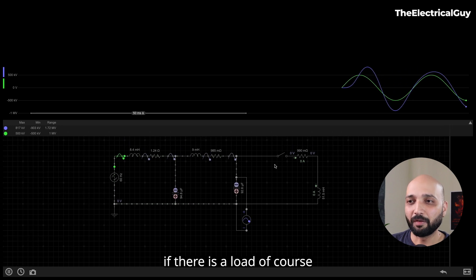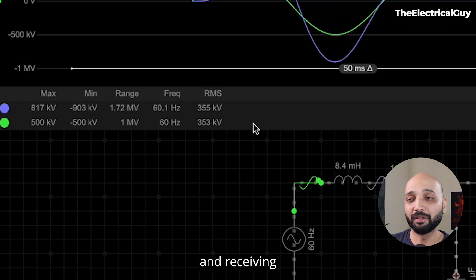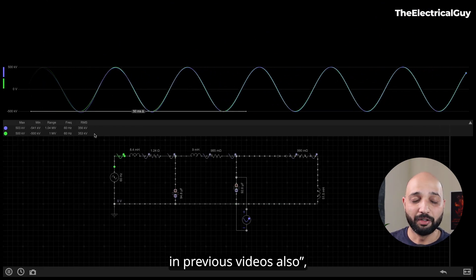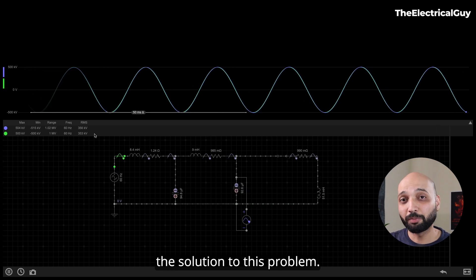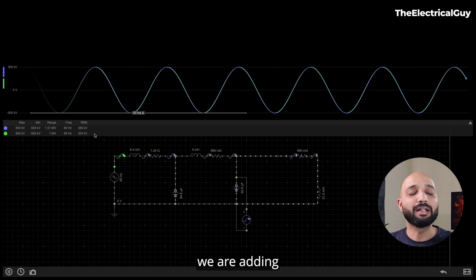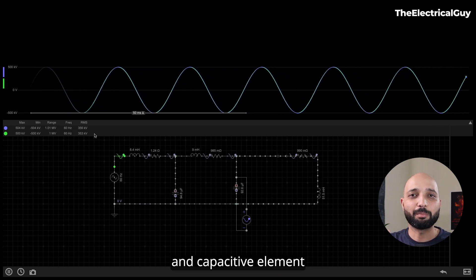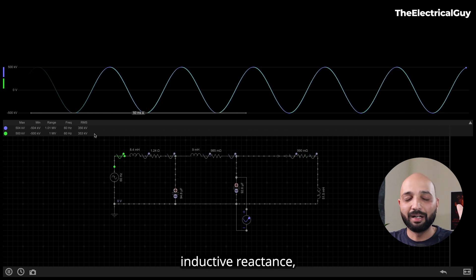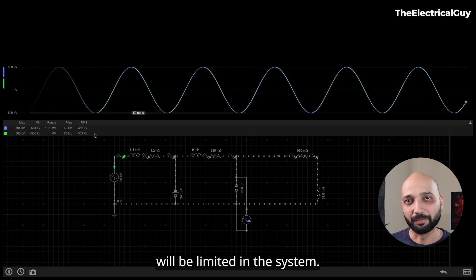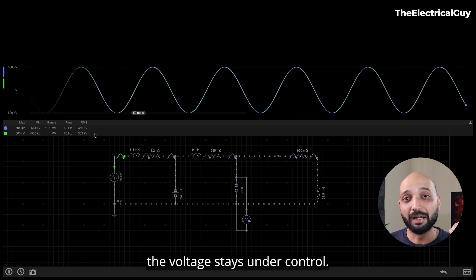If we connect load, that problem goes down — you can see both sending and receiving end voltages are nearly equal. The solution to this voltage regulation problem is to add a shunt reactor. By adding a shunt reactor we are adding inductive reactance into the system, so the capacitive reactance will not dominate. Inductive and capacitive elements are opposite to each other, so adding inductive reactance limits the resultant reactive power. With the reactor added, even if the transmission line is not loaded, the voltage stays under control.